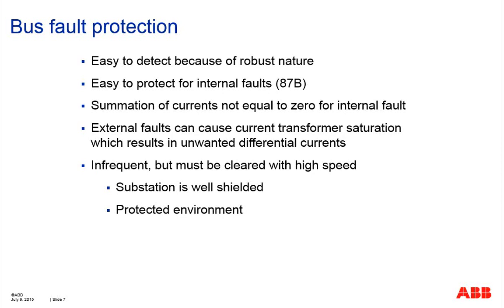However, the other characteristic of busbar is that a piece of busbar really has no significant impedance involved. Unlike a transformer, reactor, or line, where because of the distance involved and the amount of magnetic core involved, there's significant impedance. So depending on where the fault is, the fault current could be different.